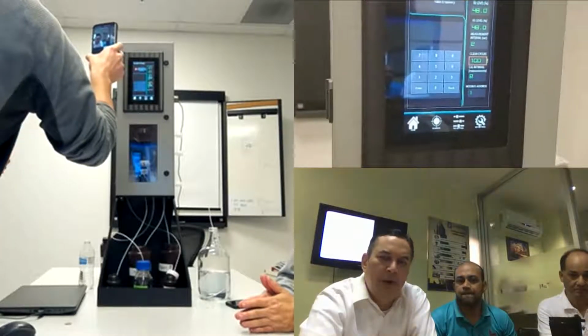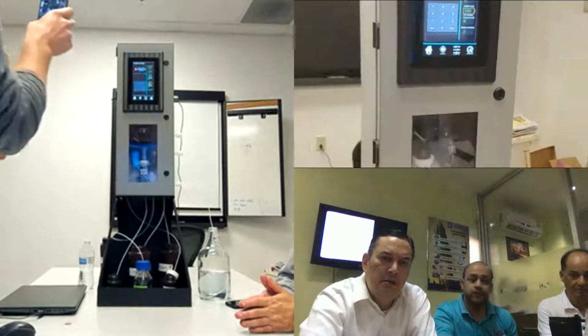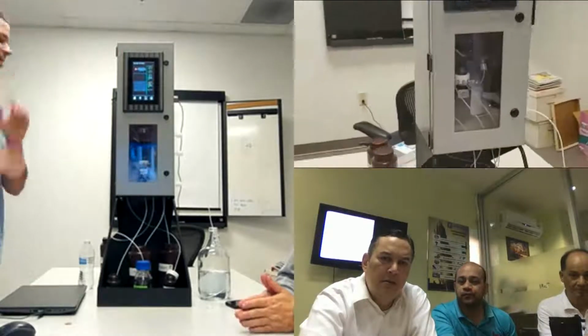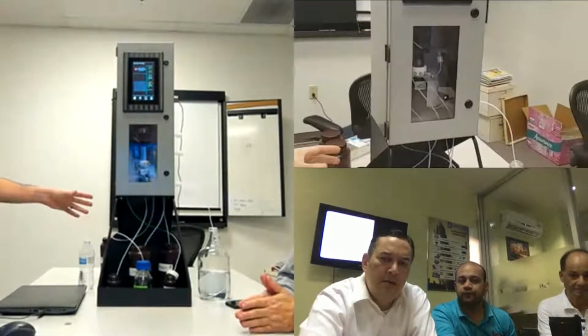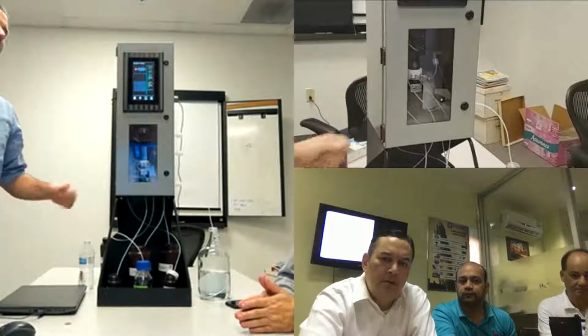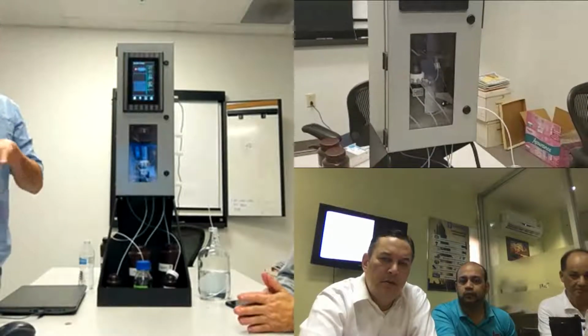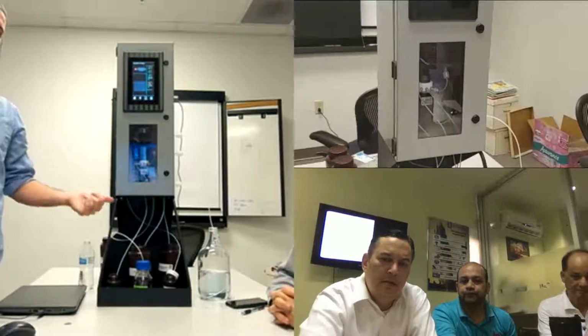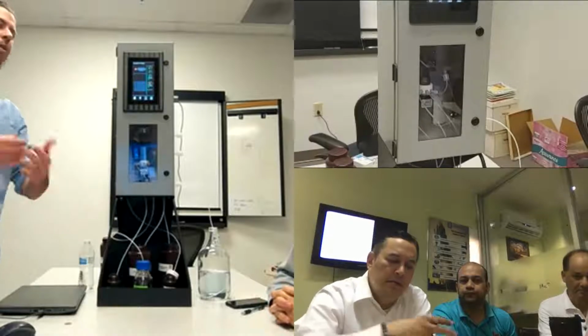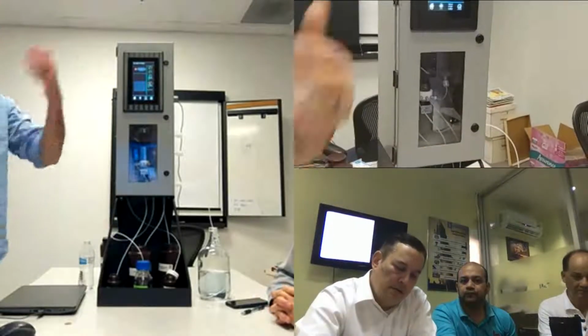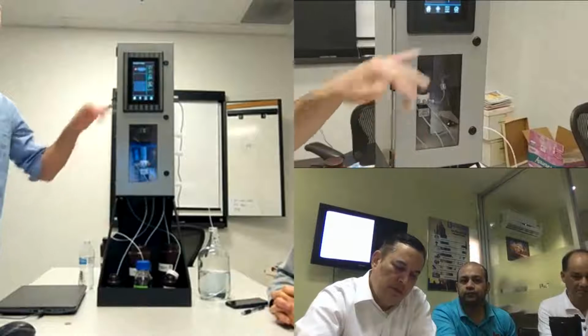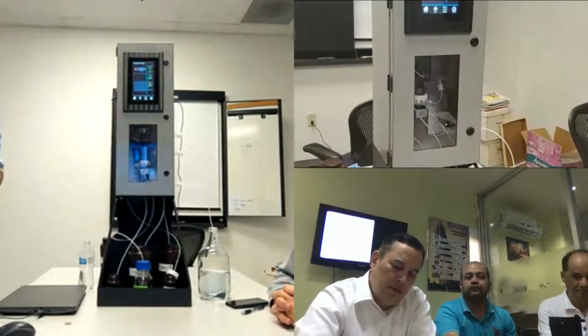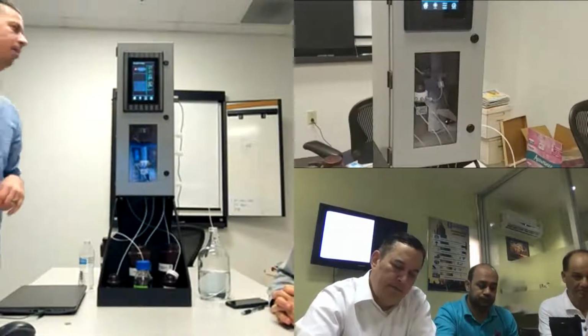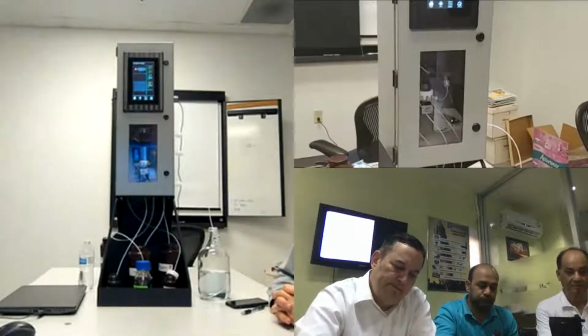That brings up another feature. It is intended that you can leave a calibration standard essentially permanently connected to the unit. So for long-term unattended measurements, you can set up an interval to automatically recalibrate the unit every 100 measurements, every 1,000 measurements, whatever you want to do. That's a variable we can set in here for automatic calibration - it's a pretty nice feature.